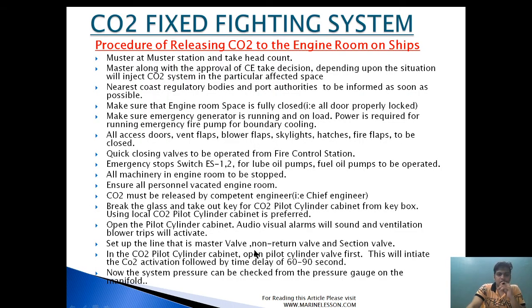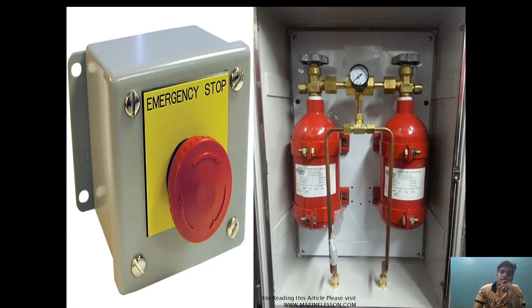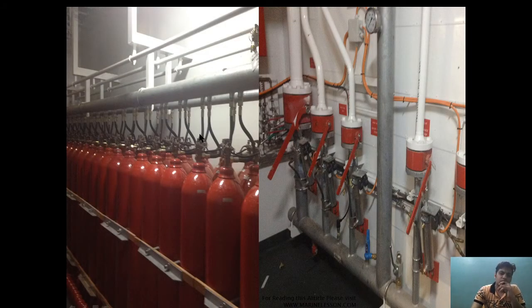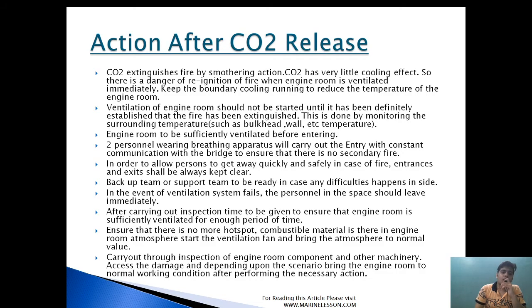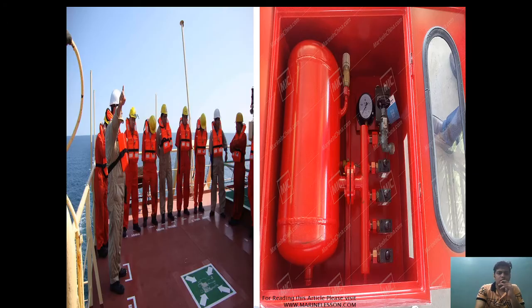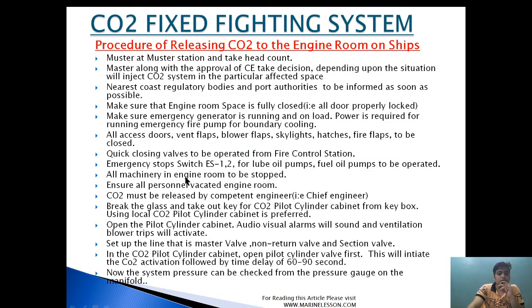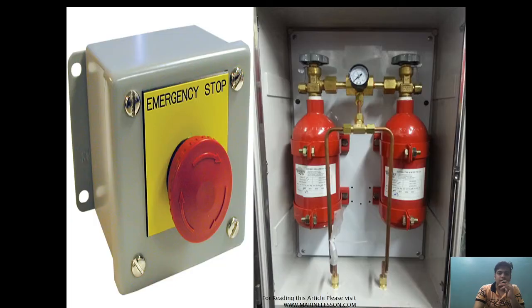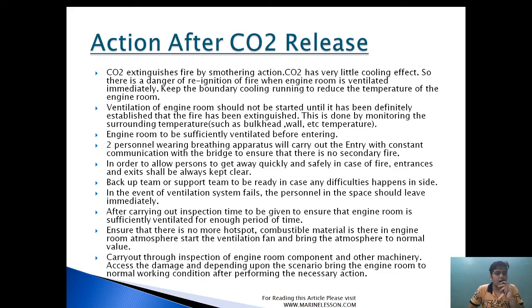Set up the line — master valve, non-return valve, section valve — then open the pilot cylinder first. This initiates CO2 activation followed by a time delay of 60 to 90 seconds. System pressure can be checked from the pressure gauge on the manifold. Opening the pilot cylinder causes CO2 to puncture the bulk system, and pressure is visible on the manifold. CO2 then travels through the section valve to the protected space to extinguish the fire. A second headcount is performed before operating the pilot cylinder to doubly confirm all personnel are clear.